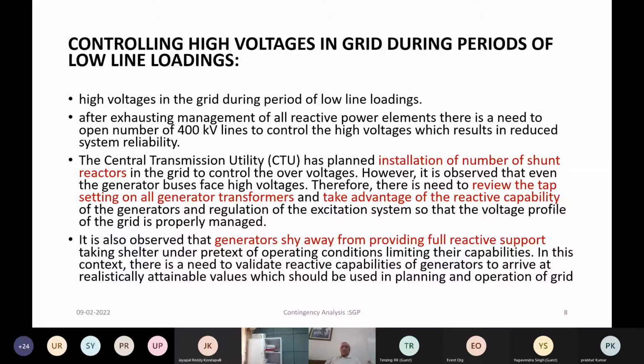Controlling high voltage in the grid during periods of low line loading is still a problem. After you exhaust all the reactive power support, there is a need to open 400 kV lines. Yesterday I had mentioned that typically a 400 kV line of 100 kilometers injects roughly 55 MVAr as a thumb rule into the grid. This causes a rise in the receiving end voltage because of the capacitive, leading reactive power being injected into the line, and the voltage goes up, which is called the Ferranti effect. So this high voltage prevention is done by opening the lines during the light load period.